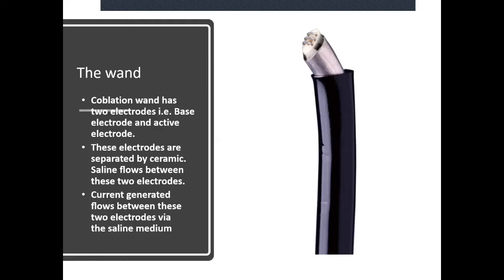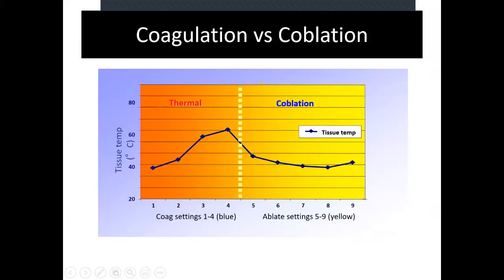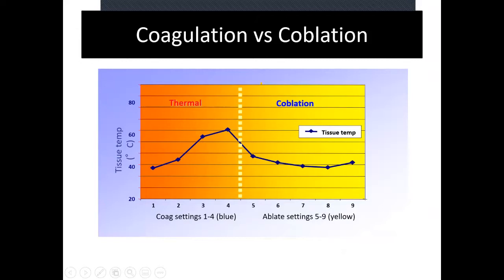There are two modes: ablation mode and coagulation mode. Always use ablation mode — don't try to use coagulation mode for ablating. If you look at thermal damage: in coagulation mode the temperature is much higher, while in ablation mode the temperature is much lower. This affects the depth of the lesion created.